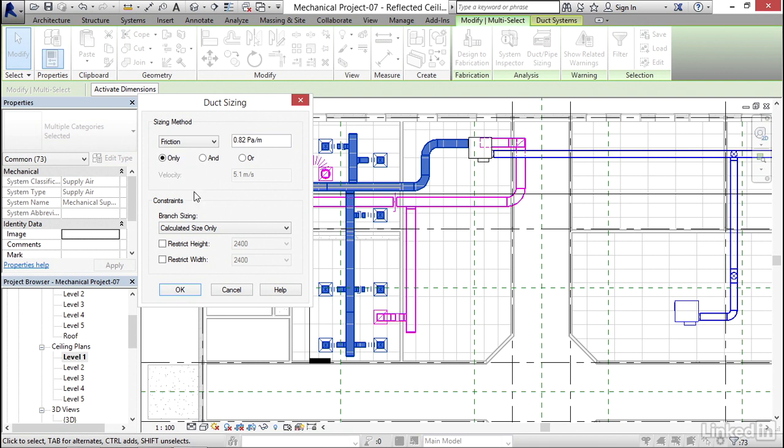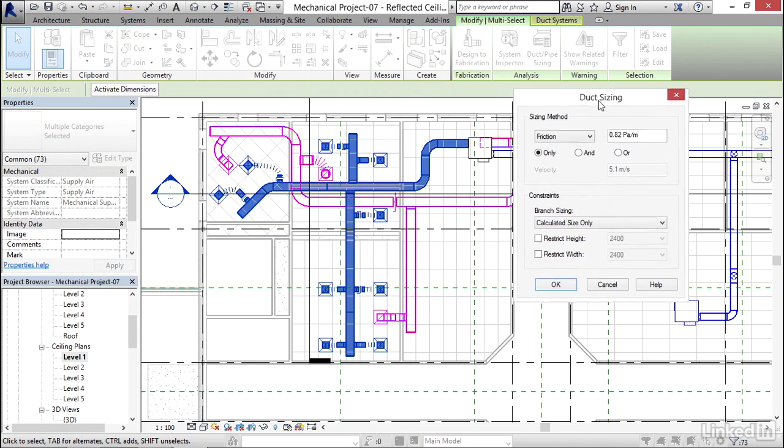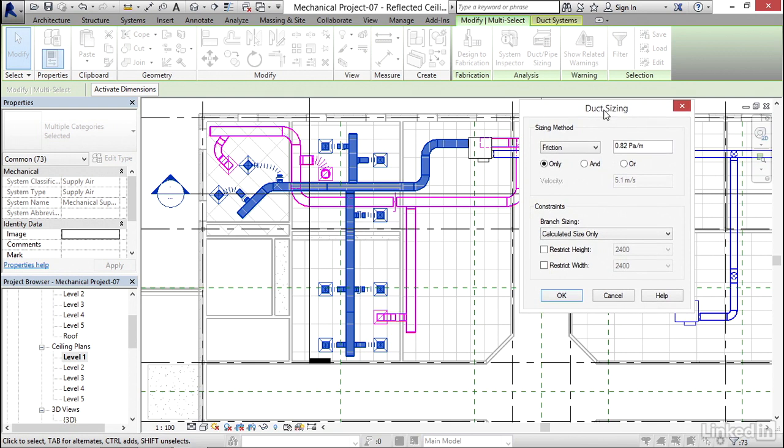I'm going to allow all of the rest of the defaults. Branch sizing, we can match connector size, or we can go to the larger of connector and calculated. Let's do calculated size only and see what happens. Because a lot of times, your fittings are going to blow up, and you have to just go back through and reconnect.